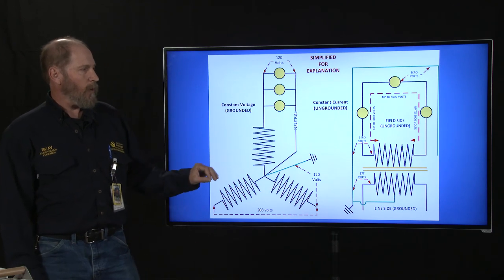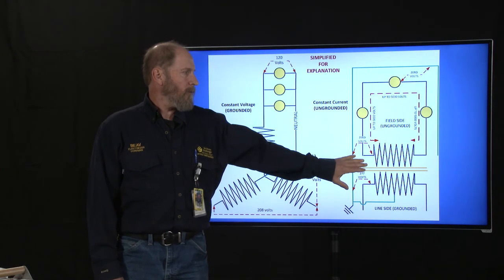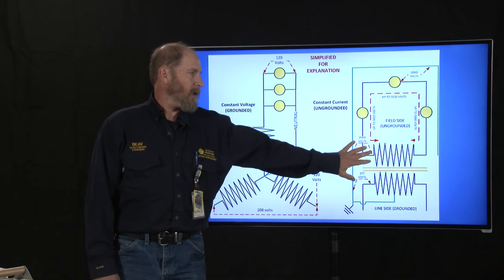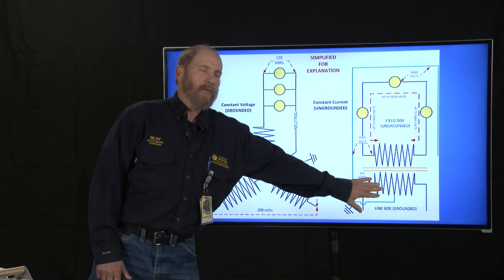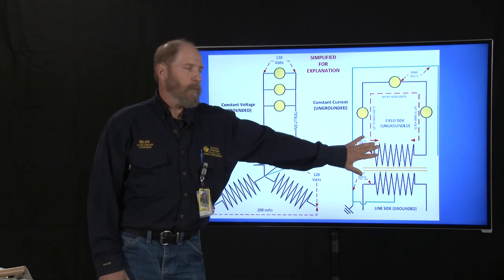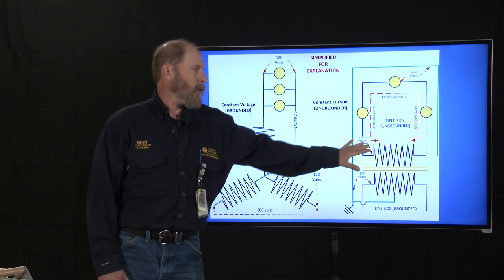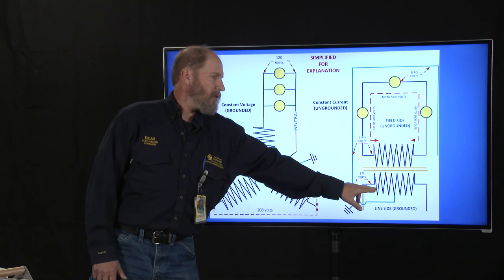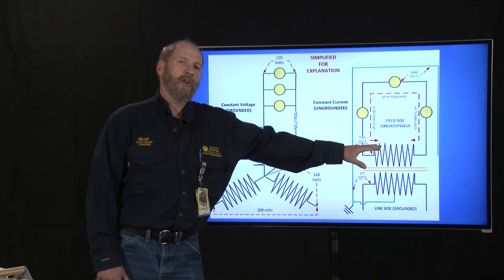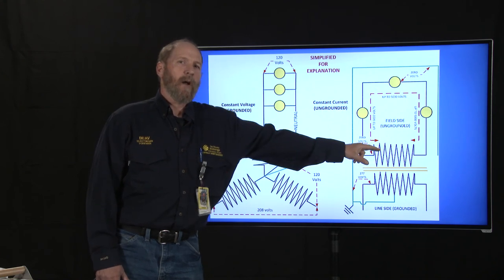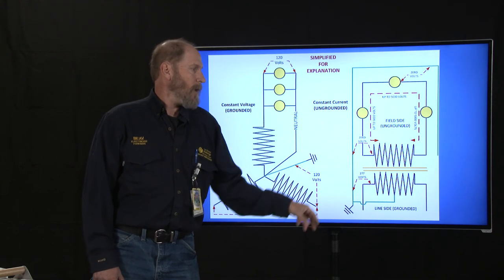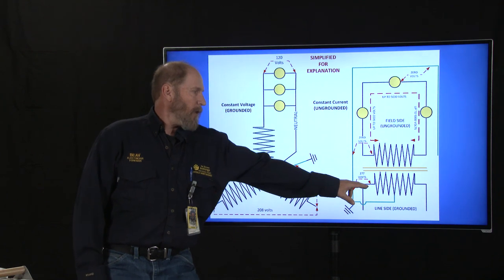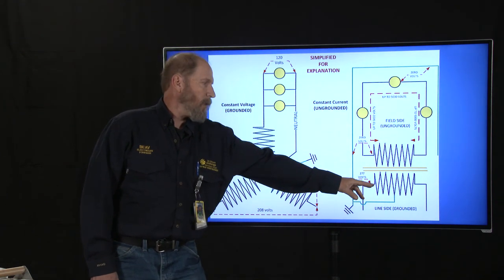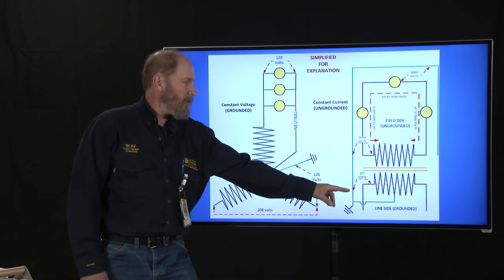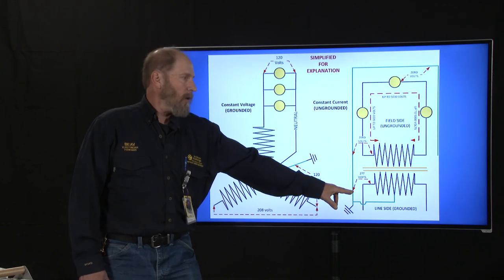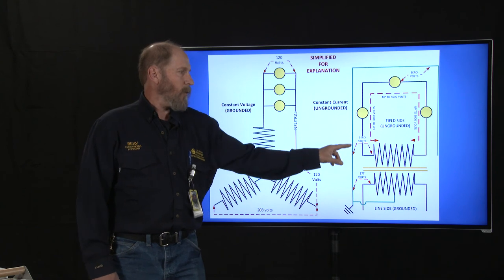Now, on a constant current transformer, the current and voltage that we're using on the field is induced through the regulator. So we have a grounded transformer on this side, and it induces a voltage and amperage across an insulated barrier to the opposite side that goes out to our field. And on this side, we're grounded. But on this side, there is no ground connected to that transformer at all. It's like it's floating. There is no ground bond. So on this side of the transformer, on the primary side, this is a 480 volt transformer, we have 480, 277 volts. So we have a 277 volt potential to ground on this side. But on this side, there is 0 volts potential to ground.